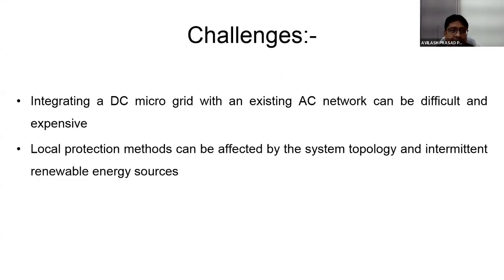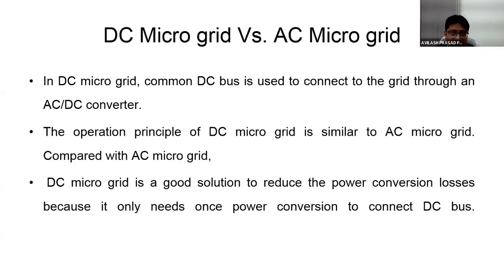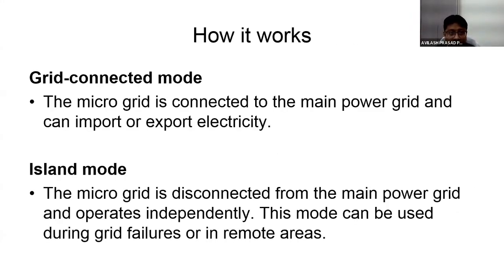Further challenges are that integrating a DC microgrid with an existing grid is difficult and expensive. It is the same, DC microgrid versus AC microgrid. In a DC microgrid, a common DC bus is used to connect to the grid through an AC-DC converter. The operation principle of a DC microgrid is similar to that of an AC microgrid. Compared with an AC microgrid, a DC microgrid is a good solution to reduce power conversion losses because it only needs one power conversion to connect to the DC bus.